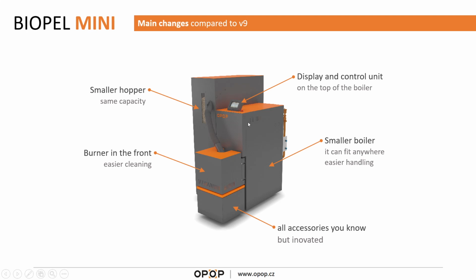So below this orange cover there is a main control unit with all the connections, so all the accessories, all the temperature sensors, everything you can access from the front of the boiler. The display itself is not installed on the top because of protection, because during transport it can happen that with the display on the top like this, the display could be damaged. So you will find the display inside the boiler, inside the ashtray, and you just put the display in position like this when you install the boiler. Okay.